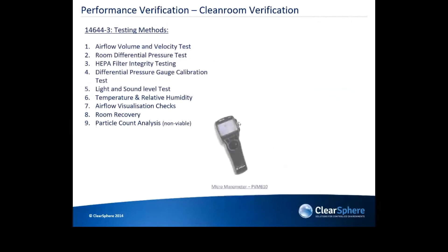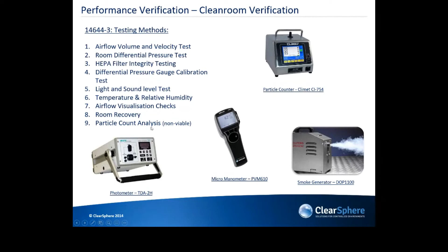So on the testing side of things, this is the sequence of testing we carried out. You've airflow volumes and velocity testing, room differential pressure testing, HEPA filter integrity testing, differential pressure gauge calibration tests, light and sound levels, temperature and relative humidity, airflow visualization and room recovery testing. Particle count analysis for non-viable, so these are purely non-viable testing.